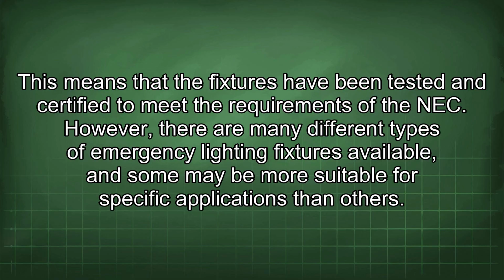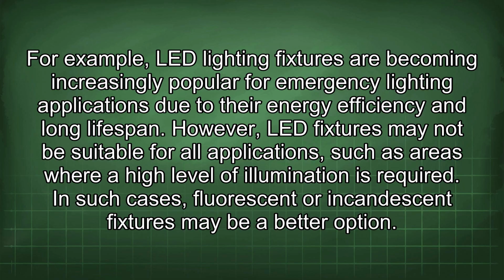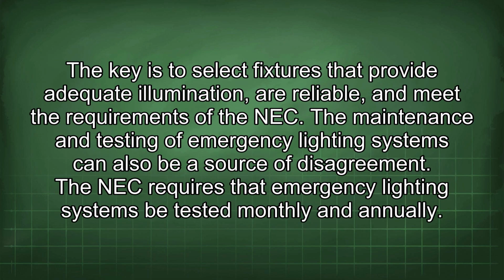than others. For example, LED lighting fixtures are becoming increasingly popular for emergency lighting applications due to their energy efficiency and long lifespan. However, LED fixtures may not be suitable for all applications, such as areas where a high level of illumination is required. In such cases, fluorescent or incandescent fixtures may be a better option. The key is to select fixtures that provide adequate illumination, are reliable, and meet the requirements of the NEC.